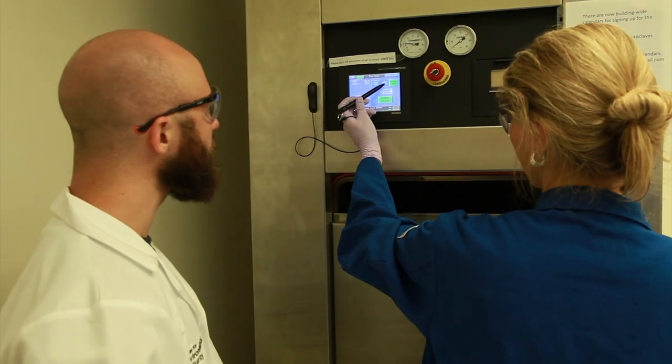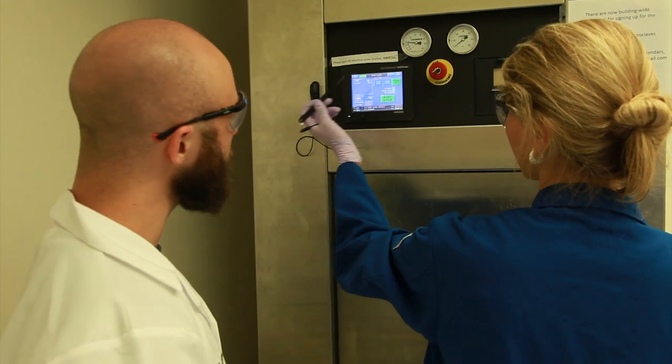A completed cycle usually takes between one to one and a half hours depending on the type of cycle. Note, it is recommended to check on the autoclave run about 20 minutes in to make sure the autoclave is working properly and reached 121 Celsius per your chosen cycle parameters. Do not attempt to open the door while the autoclave is operating. If problems with your autoclave are perceived, abort the cycle and report it to your PI immediately. Communication is key.